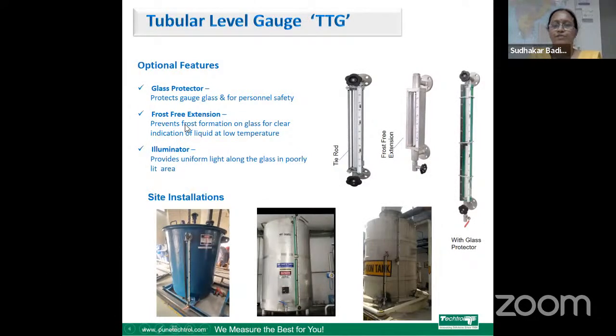So these are some optional features we provide along with these gauges. This is a glass protector for external extra safety, then frost-free extension for low temperature liquids, and illuminators for poorly lit areas. Here on the right side you can see pictures of it, the frost-free extension, and this is a gauge with coupler connection. And at the bottom side you can see the site installations. The first one is a gauge installed on the dosing tank. Then this gauge is installed in the coupler connection. Then this is an installation on the tank in a staggered manner.